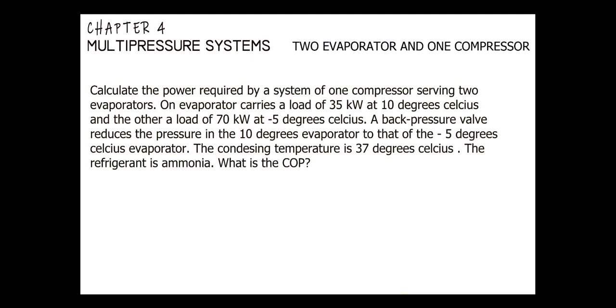We have a sample problem: calculate the power required by a system of one compressor serving two evaporators. Evaporator one carries a load of 35 kilowatts maintaining a temperature of 10 degrees Celsius, and the other carries a load of 70 kilowatts with a maintaining temperature of negative 5 degrees Celsius. A back pressure valve reduces the pressure in the 10-degree evaporator to that of the negative 5-degree evaporator. The condensing temperature is 37 degrees Celsius, and the refrigerant used is ammonia.